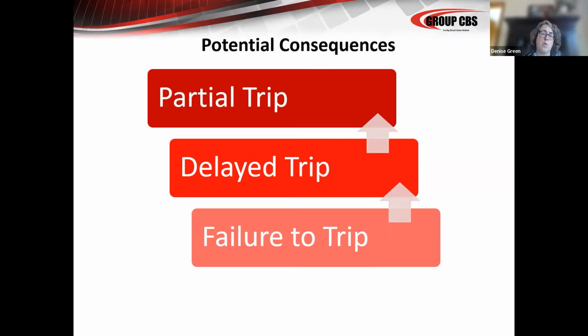The next consequence is a delayed trip, which is almost the same as a failure to trip. You have an extended stress on the cables, the bus, and that piece of equipment itself. The reason I have delayed trip a little bit above failure to trip is when that breaker does trip and you've now had your fault at a longer than anticipated time, your available arc energy is more. So when the breaker opens, you have a greater risk of physical damage to that breaker.